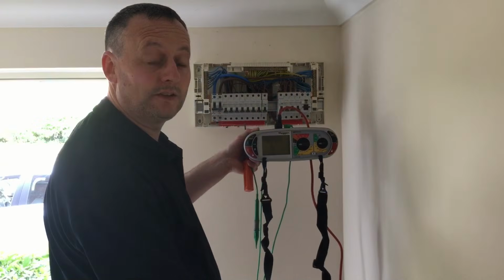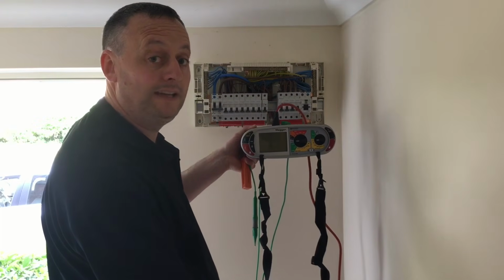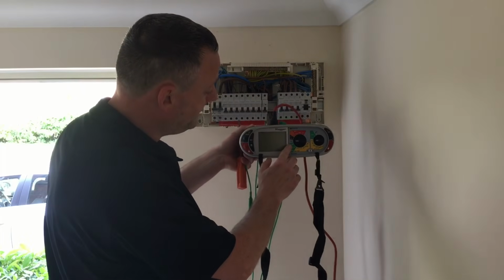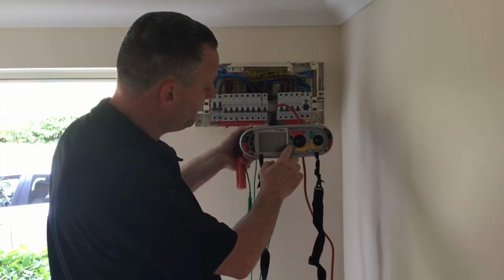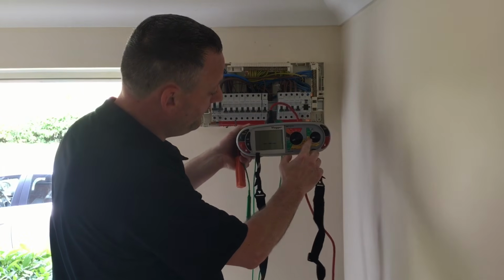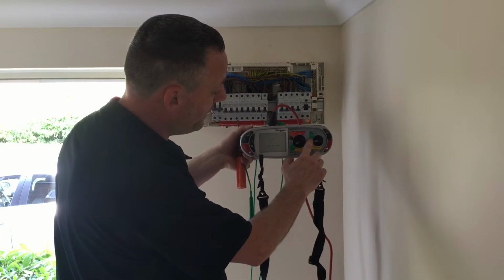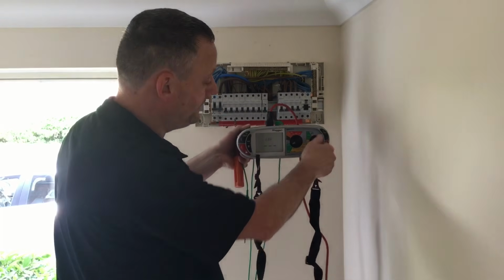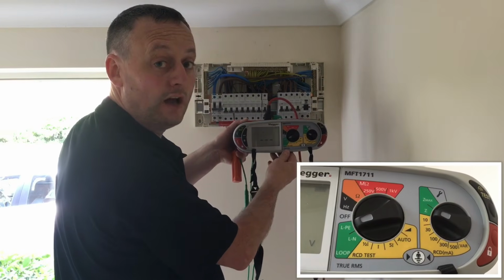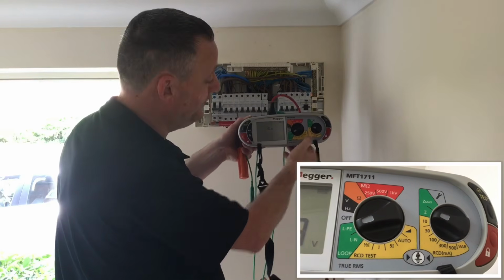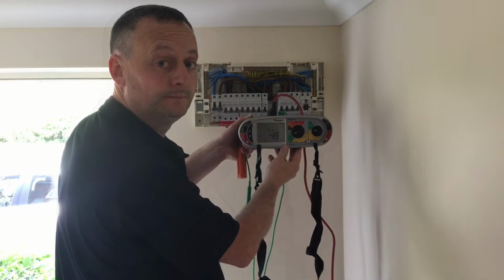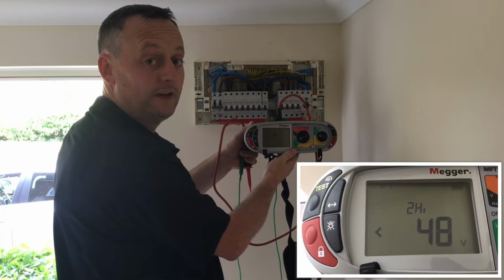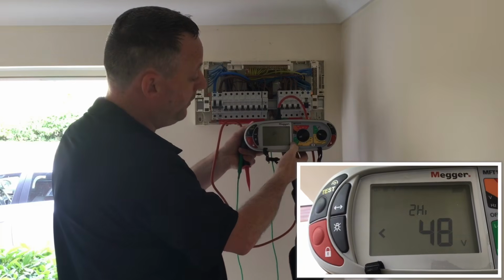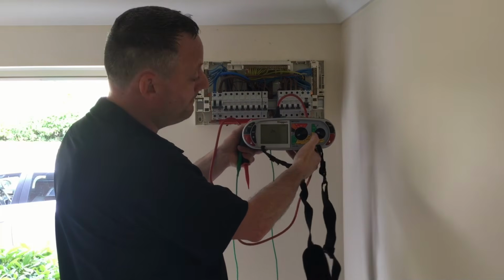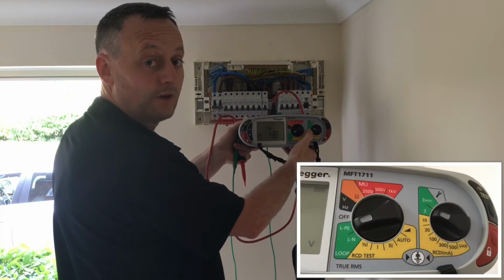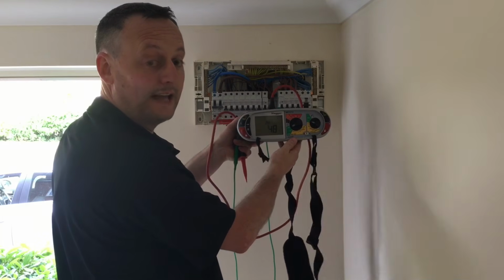In order to carry out this test, I need to set my MFT to the appropriate range. In this case, I need to go into the green section here, which is L for line and protective earth. And I need to move it on this side into the green zone against Z, Z for impedance. We're measuring the external earth fault loop impedance, and Z is representing impedance. I've set my instrument on to 2 lead high for this test. I've got the left hand one on line protective earth and my right hand one on impedance. So I'm going to carry out the test now to see what reading I get.